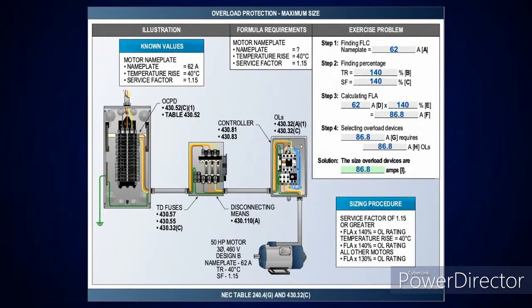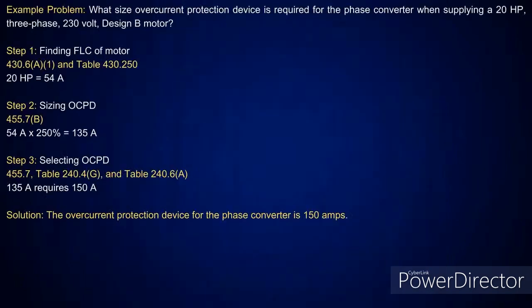Now, if I need to go to a maximum size, then you're going to look over and you're going to pick up 430.32C, and when you go pick that up, you get the exact same language. The only difference is it tells you it's 140% if you meet both of them. If you don't meet both of them, then you got to take it at 130%. Well, in this case, we just kept it the same motor, so we know we met it. So you'll just take the 62 amps at 140%, and that'll give you 86.8 amps for the overload device. All right? So up to this point, that's pretty simple.